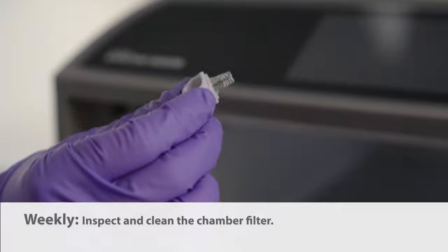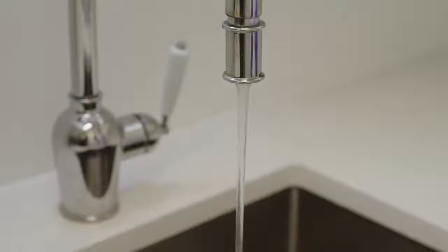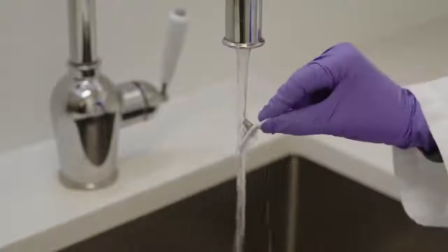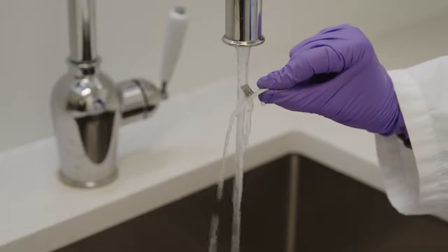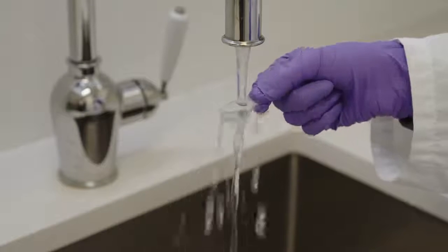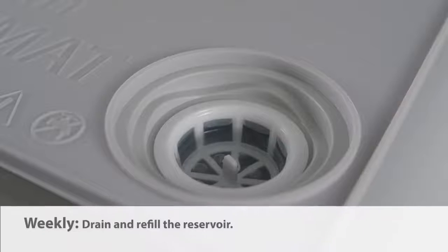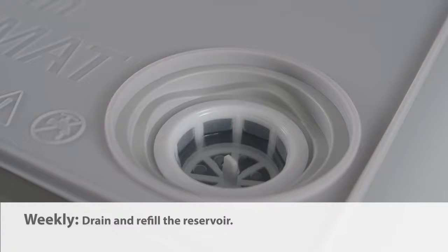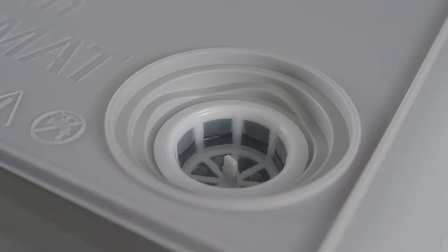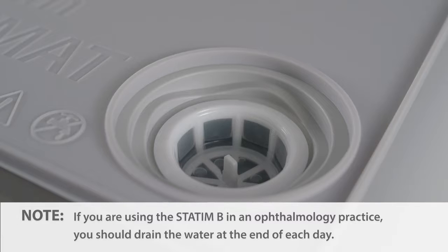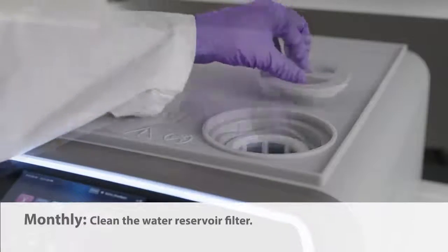To do this, remove the chamber filter and clean it under running water. Clear the mesh of any debris. If the debris cannot be removed, replace the filter. The last weekly task is to completely drain the water reservoir and refill it. Note, if you are using the STATIM B in an ophthalmology practice, you should drain the water at the end of each day. Every month, inspect and clean the water reservoir filter.